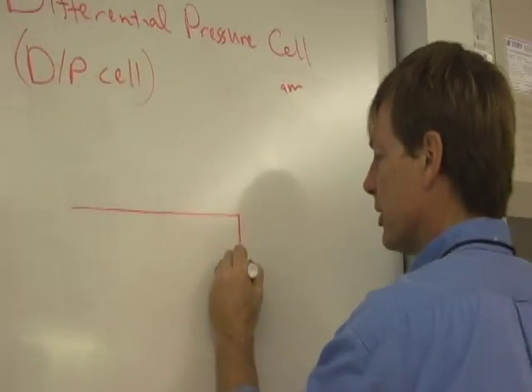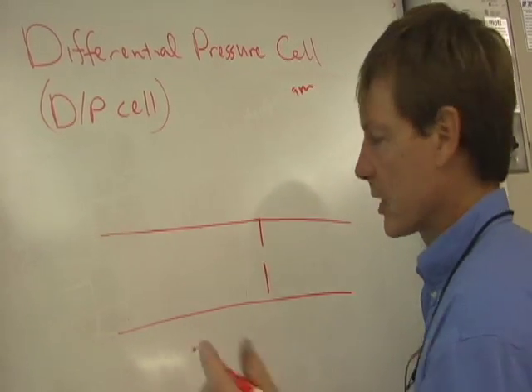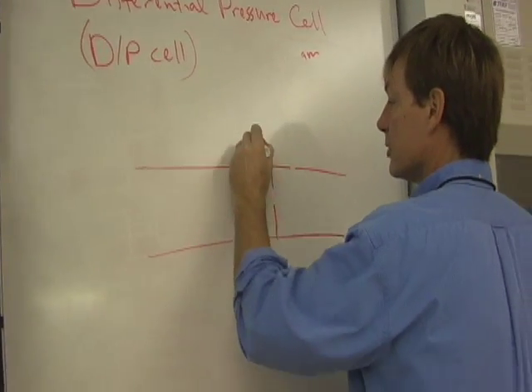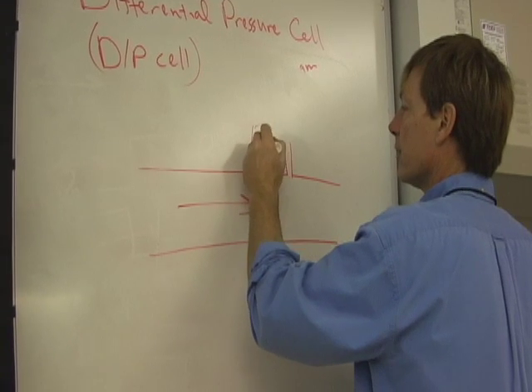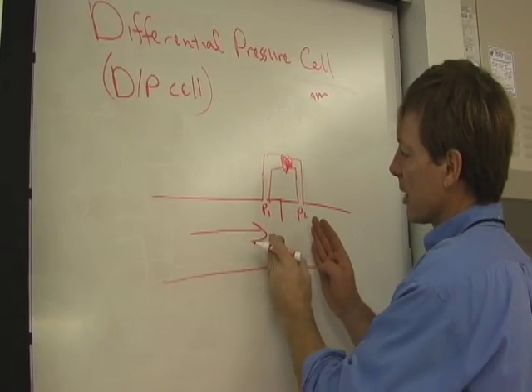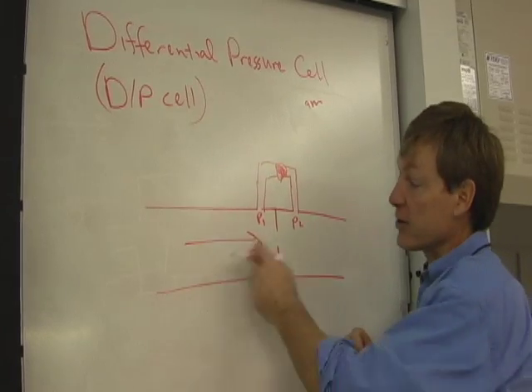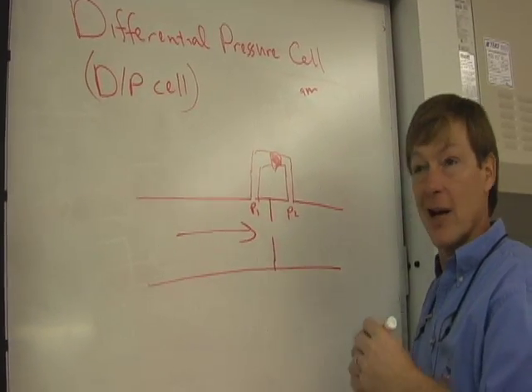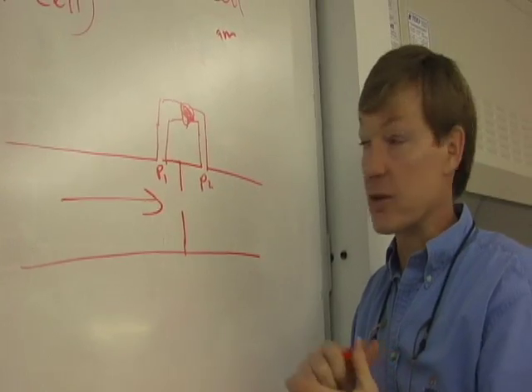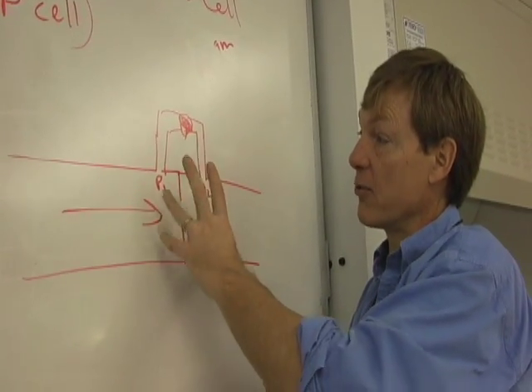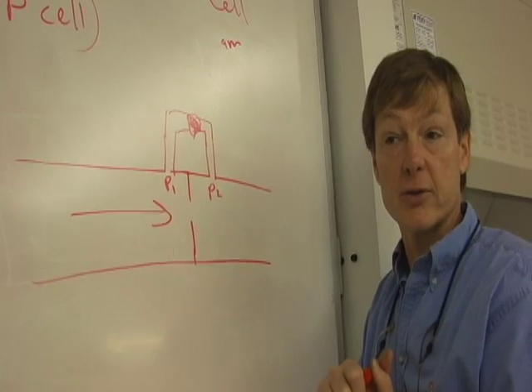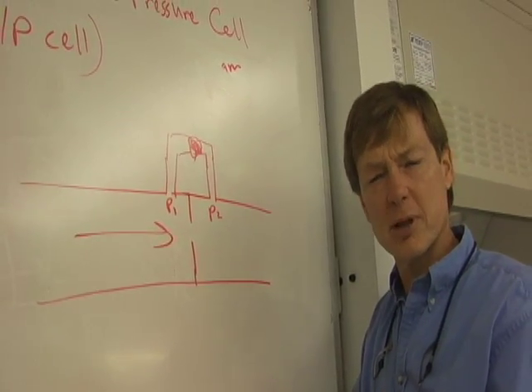And what you can do is you can stick a DP cell in. If you've got a flow tube, you're trying to get speed. Another use of them, I'm just measuring differential pressure. I can have two ports here. There's my flow, feeding into the DP cell. And across an orifice there's a pressure drop, and it depends on how fast the flow is moving. So I can calibrate a DP cell not just to measure pressure difference, but to measure flow speed by the use of an orifice. A lot of marine systems use these because they don't take that much space. They don't foul up like a turbine flow meter that has to move, and that can be a hassle. That's a good fluid flow transducer. There are others, but this gives you a pretty good snippet of what's possible.